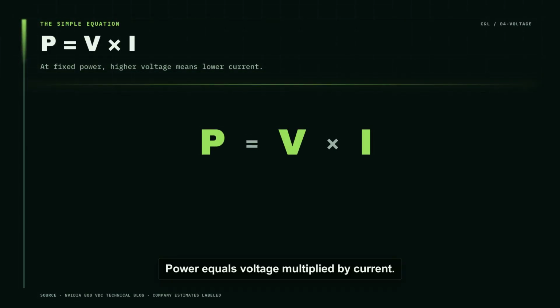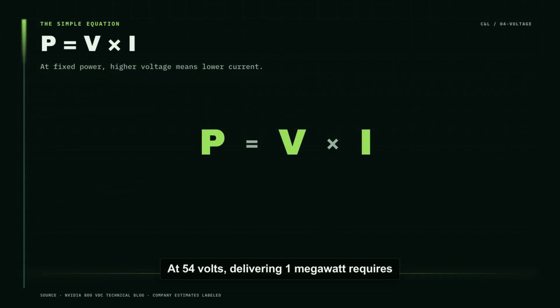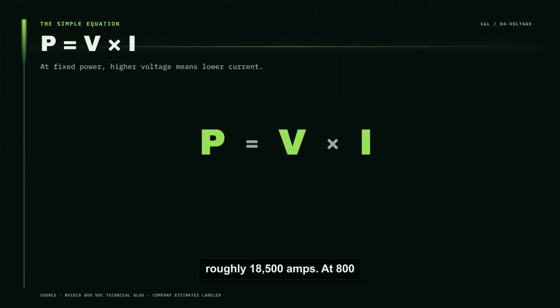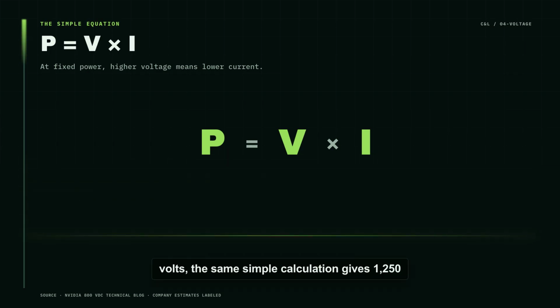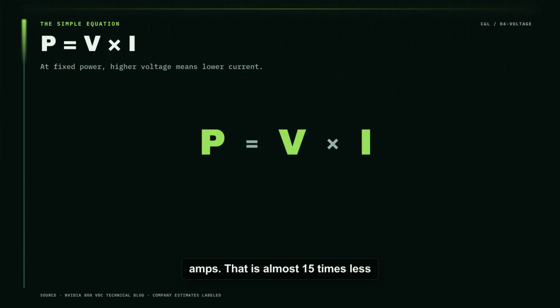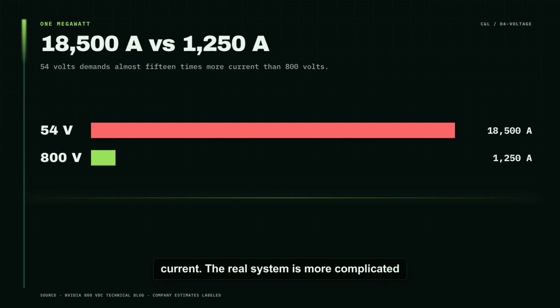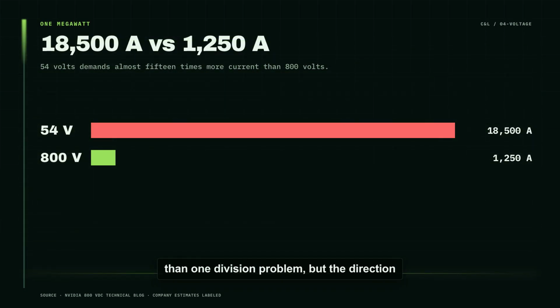Power equals voltage multiplied by current. At 54 volts, delivering 1 megawatt requires roughly 18,500 amps. At 800 volts, the same simple calculation gives 1,250 amps. That is almost 15 times less current. The real system is more complicated than one division problem, but the direction is unavoidable. Low voltage demands enormous conductors.